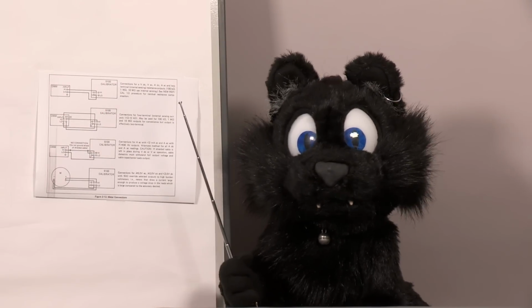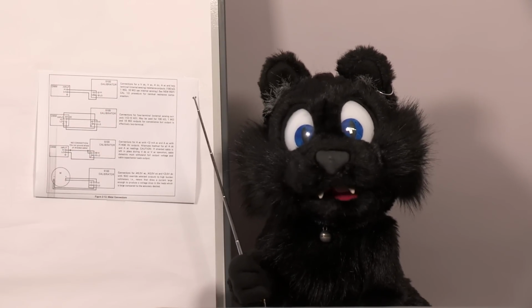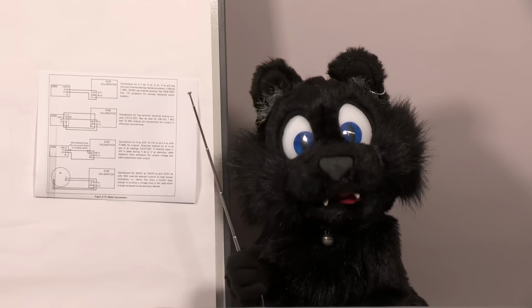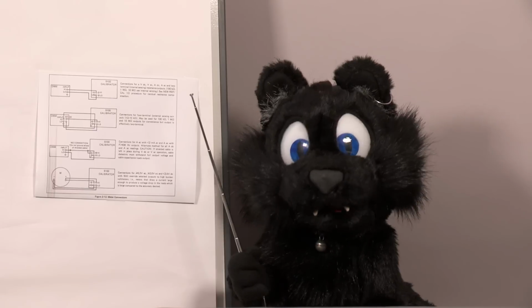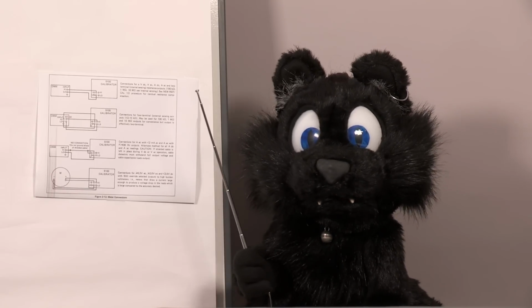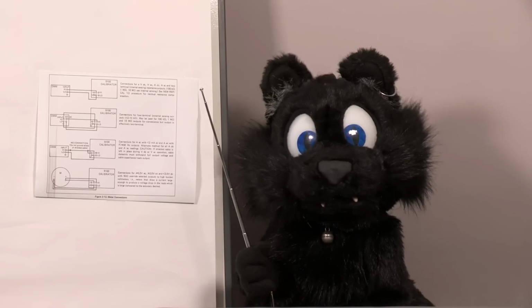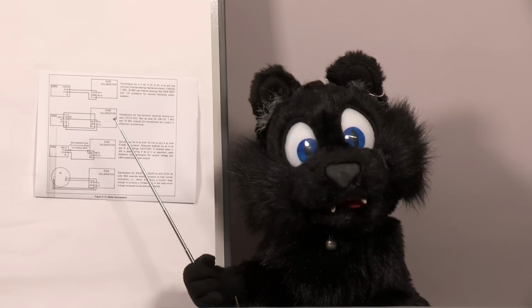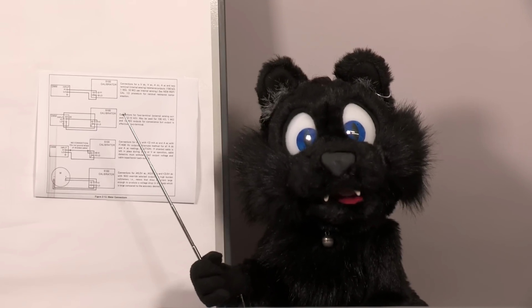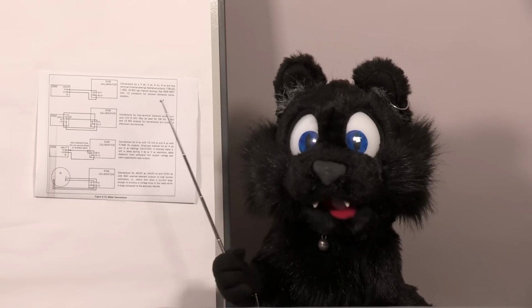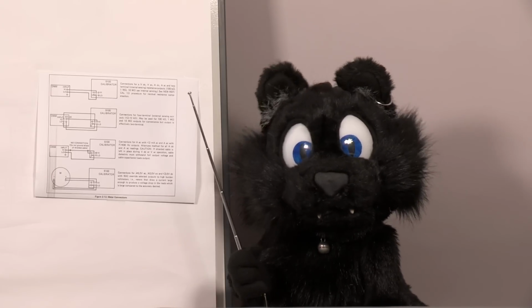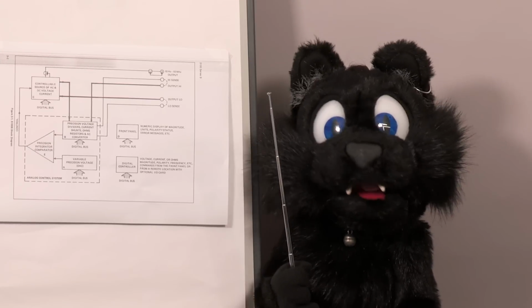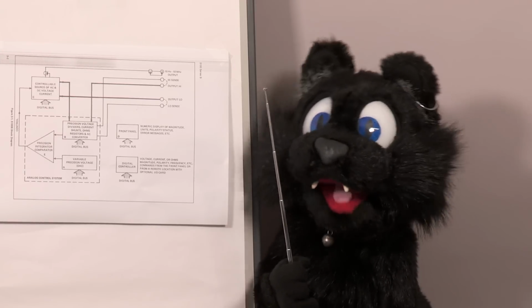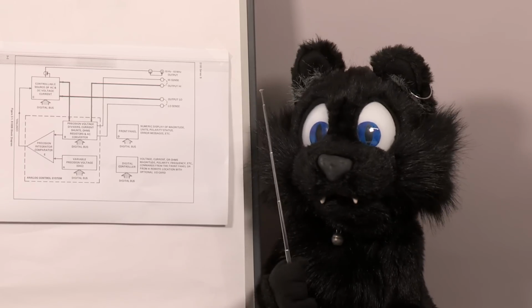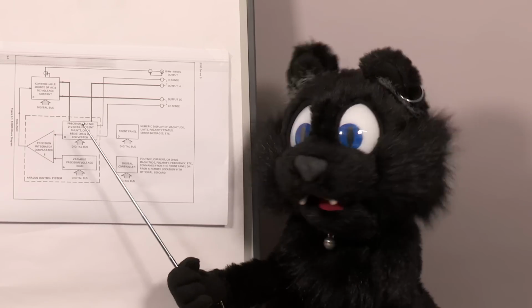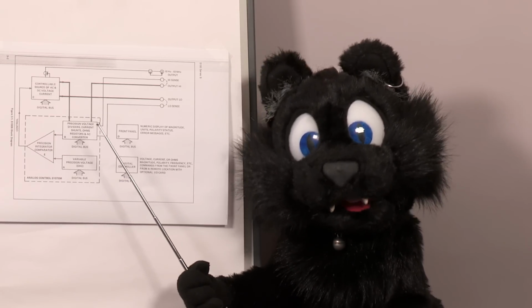At the very basic level, this device is a high-precision regulated supply. It is not geared towards power, however. That is, the output is only ever going to be a few watts tops. Just enough to drive a connected meter, no practical load. So in current mode, it is expected to have hardly any voltage, and in voltage mode, it is expected to have hardly any current. All the different relays on the PCB make for a whole lot of different configurations of the circuitry. Different parts are put into play or removed based on the operation mode and range requested.